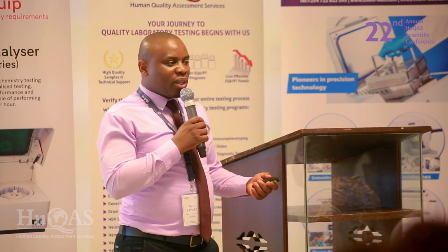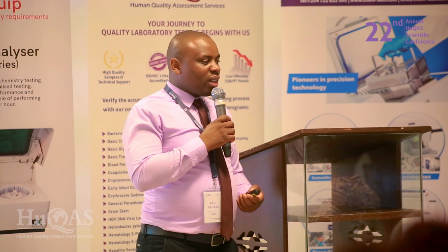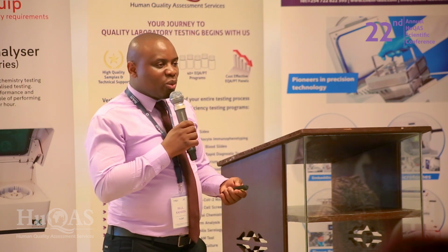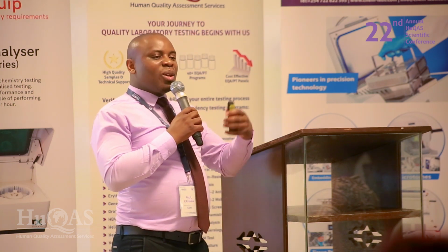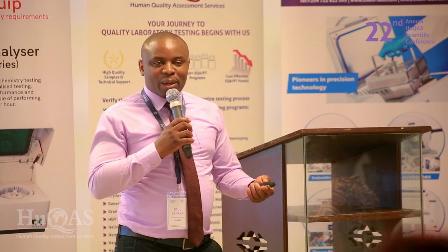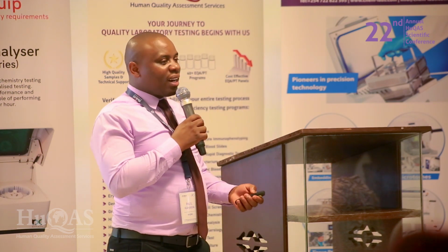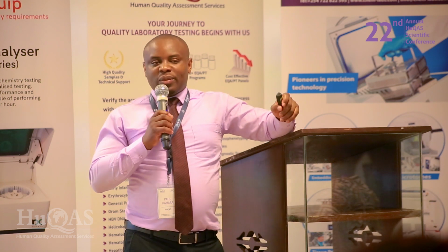Then it calls us now to talk about an agreement with them. What are they supposed to do as point of care operators? What maintenance are they supposed to do? Are we the ones to carry out IQC for them? Are we the ones to carry out EQA for them? Are we the ones to carry out maintenance for them? So the standard talks about having an agreement in terms of what the POCT operators must do.